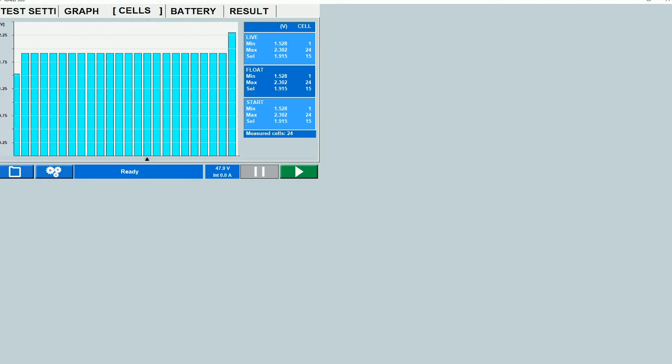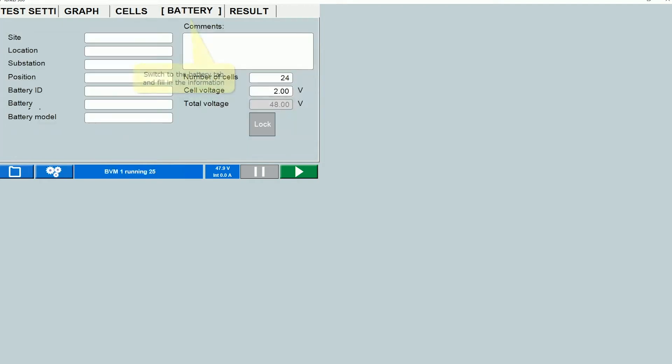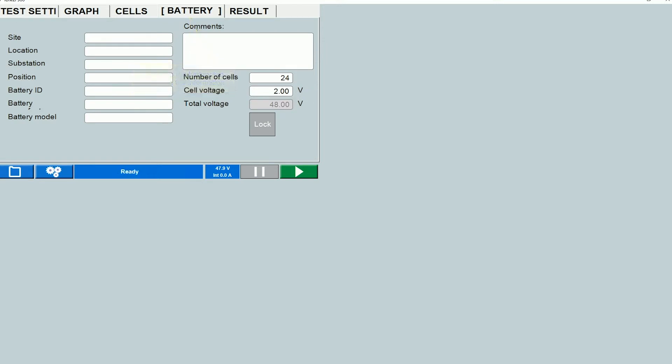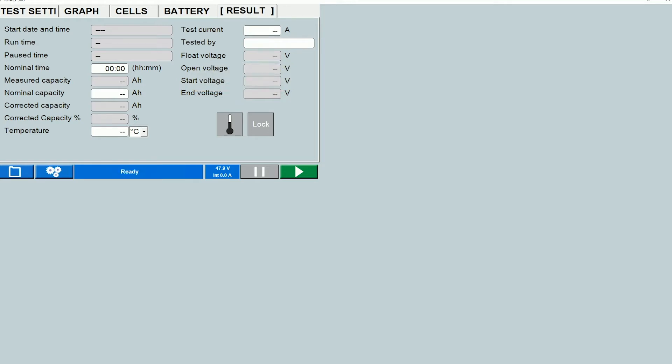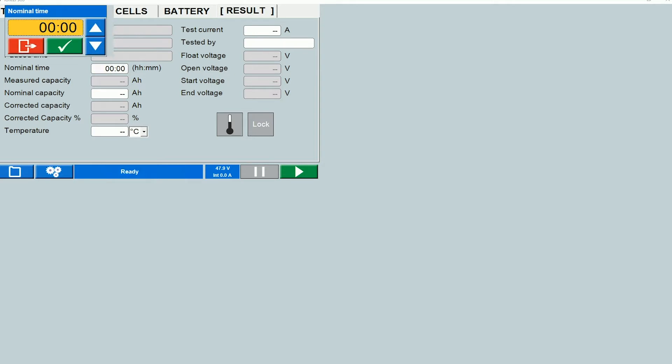And then what you will do is you would switch over to the battery tab, enter all the information on the battery string over here, go to the results tab. The results tab shows you a summary of the test data at the end of the test so you'll see that most of the fields under this tab are grayed out. They populate automatically at the end of the test but the ones that are editable you can fill in information in those fields. So let me just put in some values here.